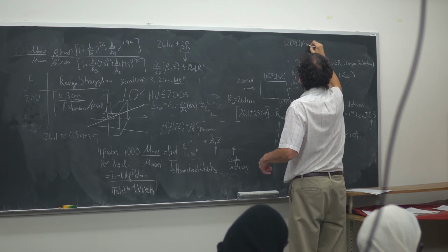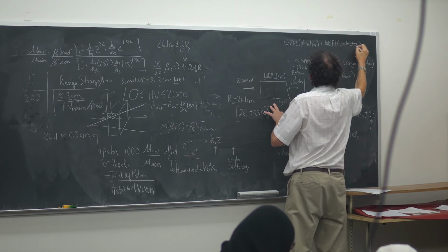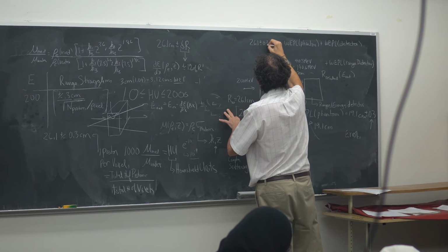All right. So basically, let me see if I can write it a different way again. The WEPL of the phantom plus the WEPL of the range detector must add up to 26.1 plus or minus 0.3 centimeters. That's what I meant to write.